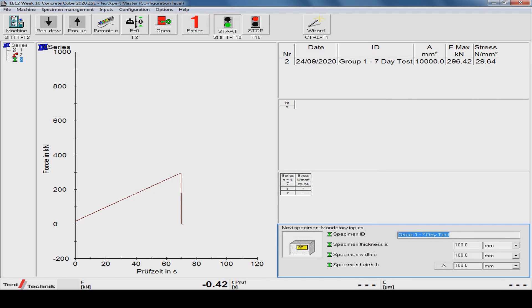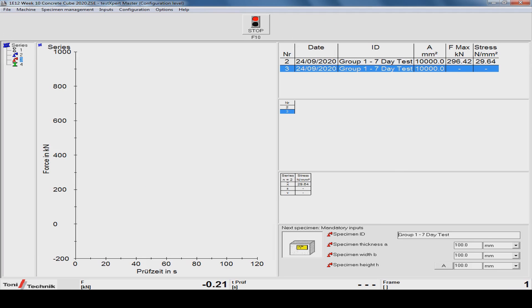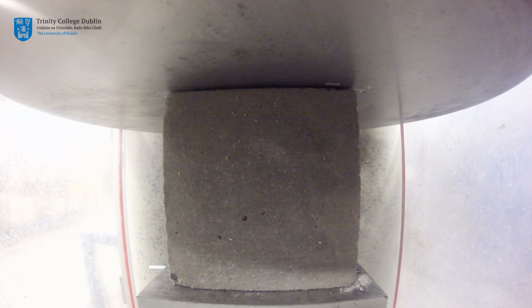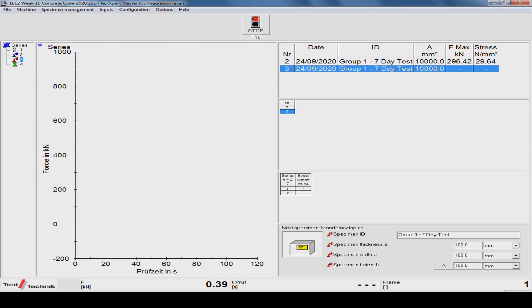The testing machine is then started, again via the software. The bottom platen of the machine moves up under hydraulic power until the specimen is in contact with the top platen. The desired test rate is then applied to the sample.